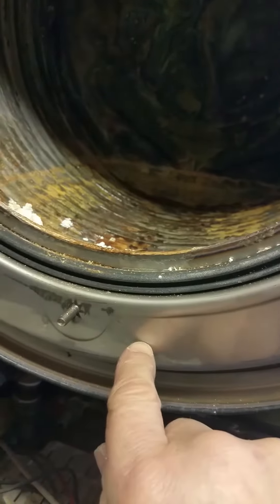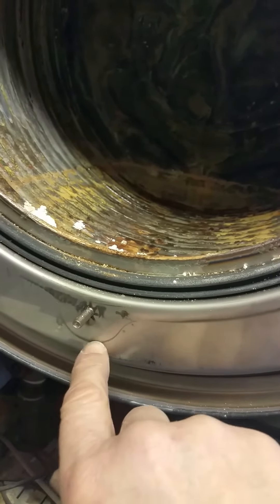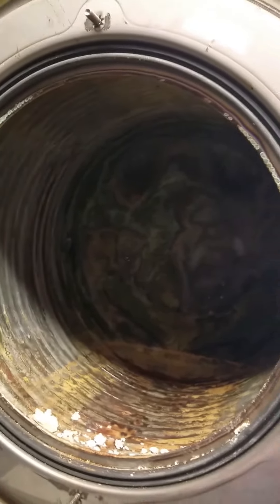If you installed the boiler leaning forward, the condense used to sit against the aluminium panel and rot through the heat exchanger. Viessmann were claiming the boiler had to be level but wouldn't give any idea of how level.